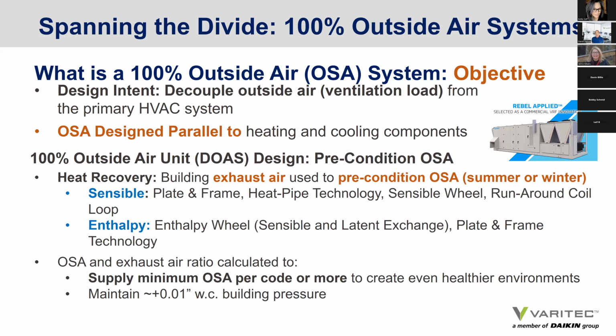A 100% outside air system is decoupled from the HVAC system. That is to say, in your sensible dehumidification mode of cooling in conventional HVAC systems, we handle the outside air independently and design it parallel to your other VAV, your other mechanical HVAC system in a building. Well, one of the efficiency advantages of a 100% outside air unit is that they are frequently designed with energy recovery that actually uses exhaust air, and it's either warmer or cooler condition depending on the season, to precondition the outside air without using mechanical forced cooling or heating.